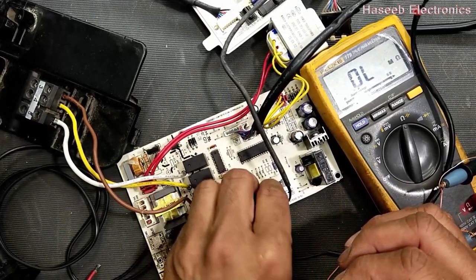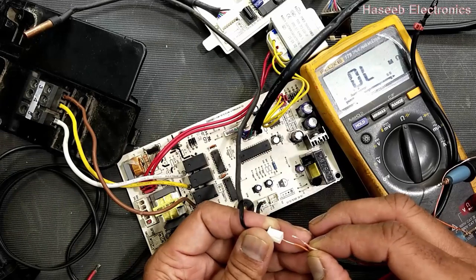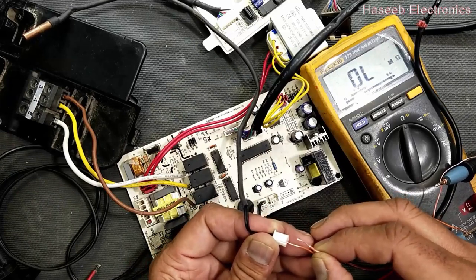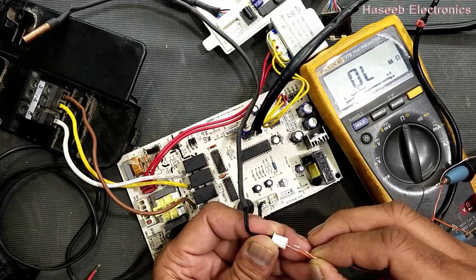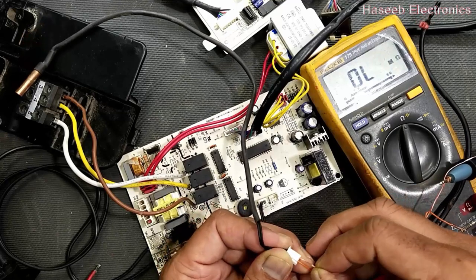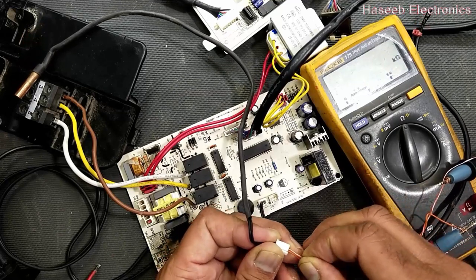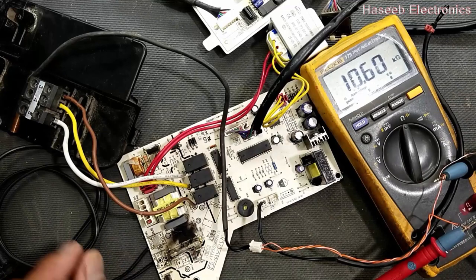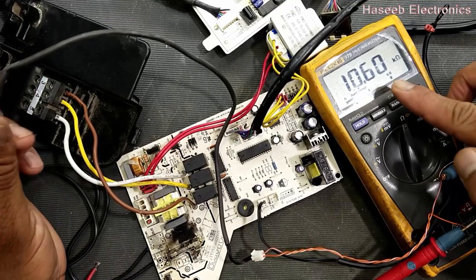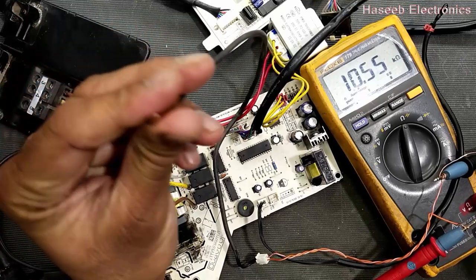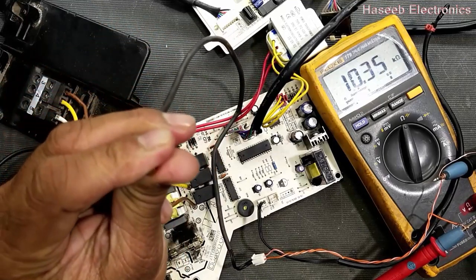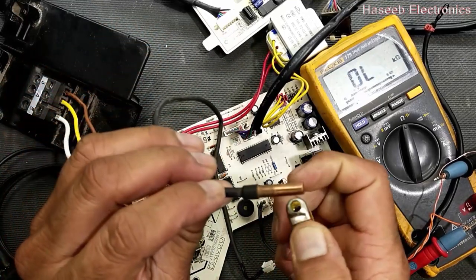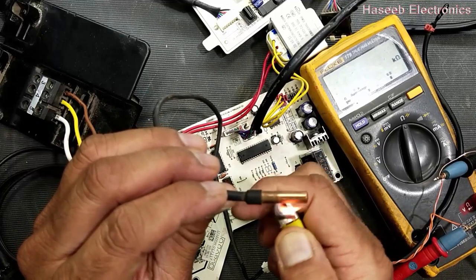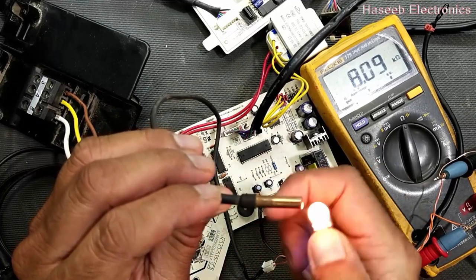It is a quick test. We can also provide a specific controlled temperature and monitor it. Check the pipe temperature sensor. Some boards have 15 kilo ohm, this one is 10 kilo ohm. The same way, hold it in fingers, or we can apply some heat.